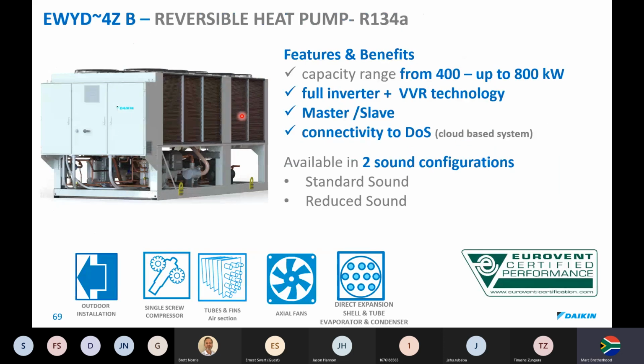This is pretty much what the unit looks like. It works on 134A refrigerant. We start from 400 kilowatts up to 800 kilowatts, fully inverter, as well as the variable volume ratio technology, connectable to Daikin on site, and it comes with 2 sound options. These are important if you select these kind of chillers, say for hospitals. Sound, or noise, is a big factor for hospitals, for patient recoveries.